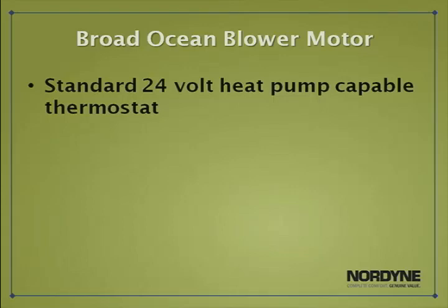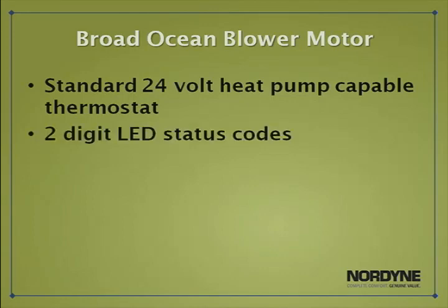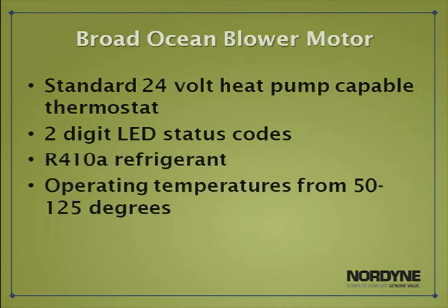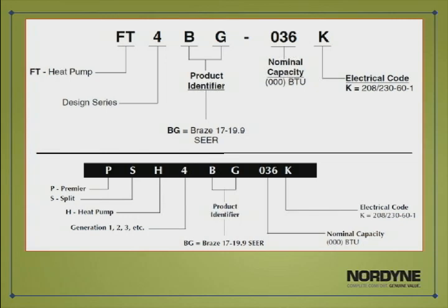Installers and homeowners will both appreciate the simplicity of being able to use a standard 24-volt heat pump capable thermostat. Service technicians will have the availability of 2-digit LED status codes and diagnostic troubleshooting information. The condensers use R410A refrigerant and have operating temperatures from 50 to 125 degrees. Here's an example of how the model numbers will break down.